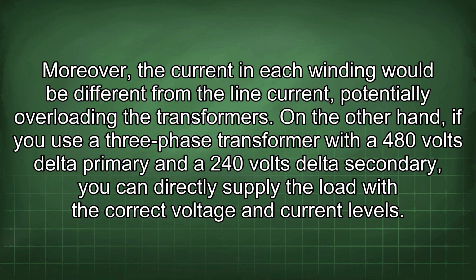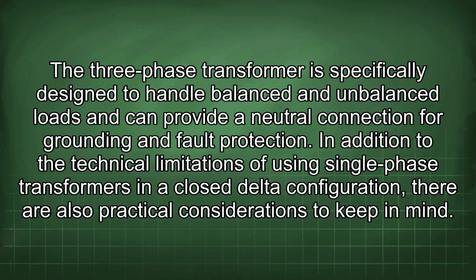On the other hand, if you use a three-phase transformer with a 480 volts delta primary and a 240 volts delta secondary, you can directly supply the load with the correct voltage and current levels. The three-phase transformer is specifically designed to handle balanced and unbalanced loads and can provide a neutral connection for grounding and fault protection. In addition to the technical limitations of using single-phase transformers in a closed delta configuration, there are also practical considerations to keep in mind.